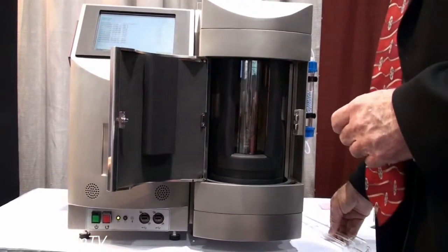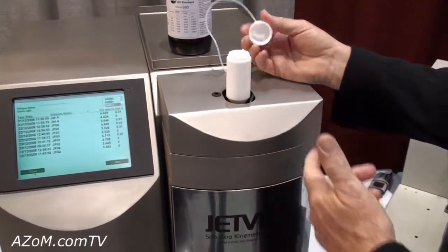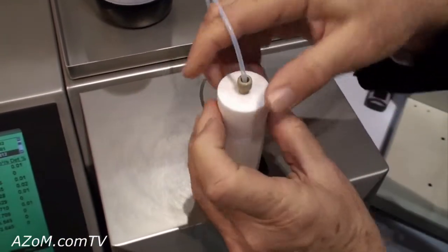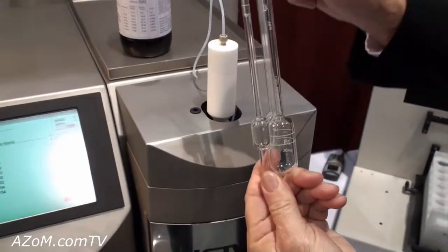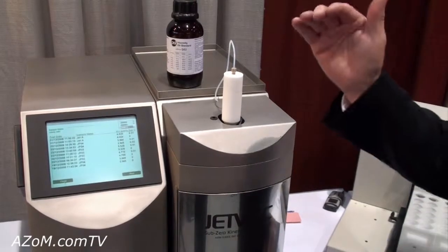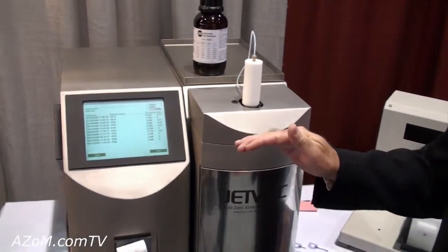The operation of the system is, we think, quite unique. We've developed what we call a filling station. The sample is syringed into the filling station, at which point the sample falls into the glass capillary viscometer. The temperature bath would automatically ramp, pull the sample up, dry the viscometer, and drop it to minus 20 to let it stabilize.